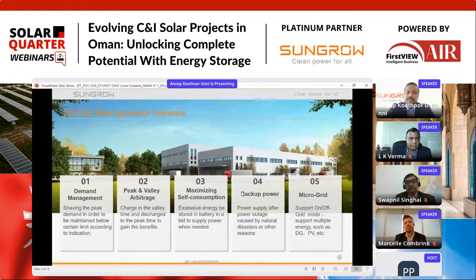So the first is the product's application area. The product is mainly focusing to service in the C&I area. One is for demand management, where we have excess power, that power saving. The second one is peak shaving and arbitrage, so in the lower times, like early morning and early evenings, you can charge it, and whenever you have daytime peaks and evening time peaks, you can discharge the battery. The third one is maximizing the self consumption — for example, if the grid limit is there and you have excess energy from the PV, you can store it and discharge it. The fourth case is pure off-grid, like a backup power system. And the last one is microgrids, which makes integrations with DG, PV, etc.